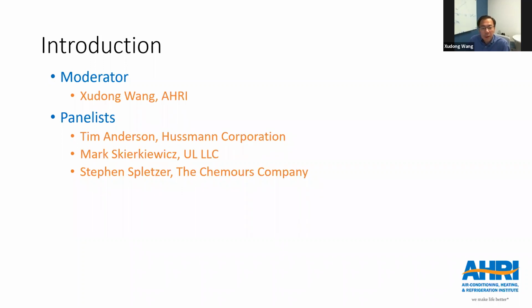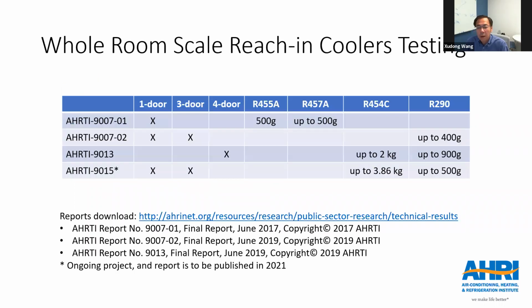So next slide, please. Over the past 3 years, AHRI's research arm has conducted many whole room scale refrigerant tests in several refrigerated display cases. If you go to the next slide, you will see the summary of the testing we have done. We tested display cases with A2L and A3 refrigerants at multiple charge levels and different scenarios. Our testing goal was to generate some test results and provide technical data to relevant safety standard committees for updating standards.